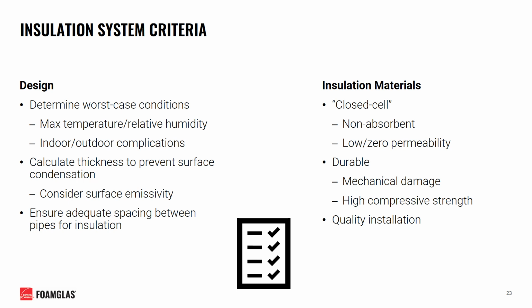As we've now learned, there are multiple factors that go into designing a successful insulation system for your chilled water applications. As a recap, when designing your system, you'll want to always determine the worst case conditions of your environment and plan accordingly. This includes the max temperature and relative humidity to be expected, as well as any indoor-outdoor complications that may be applicable. You'll want to be sure to calculate the thickness necessary to prevent surface condensation, taking into account the emissivity of the jacketing that will be used. And finally, be sure to allocate adequate spacing between and around pipes for the insulation to be installed.